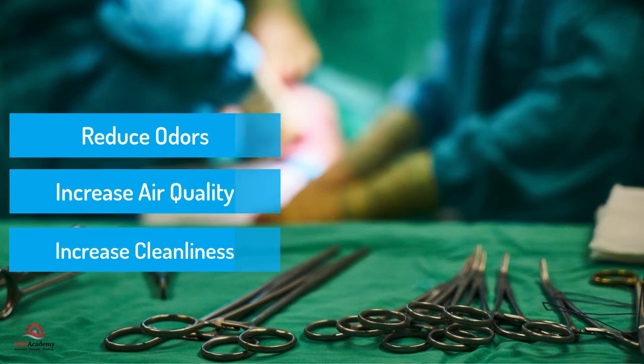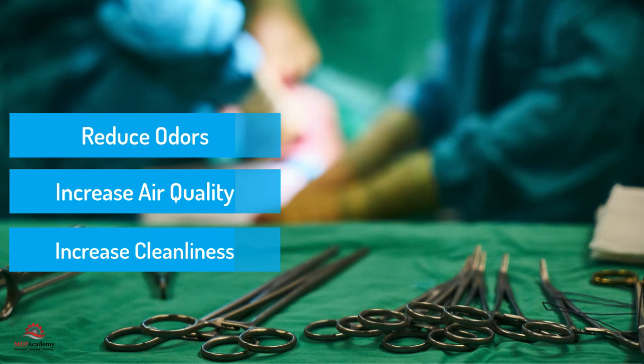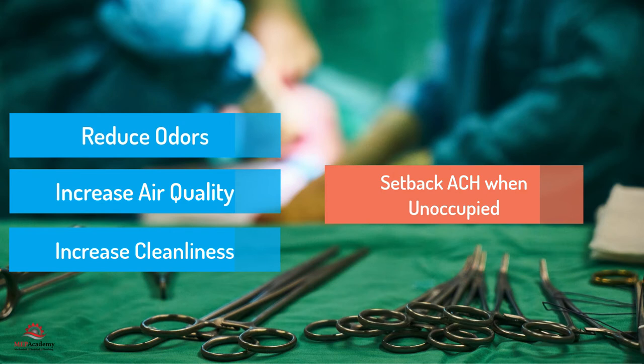There is obviously a cost to increasing the quantity of air changes due to the consumption of fan and/or compressor power. Providing the correct amount of air changes and no more is critical to providing an energy-efficient system. When critical spaces are unoccupied, air changes should be set back to lower volumes or turned off if allowed.